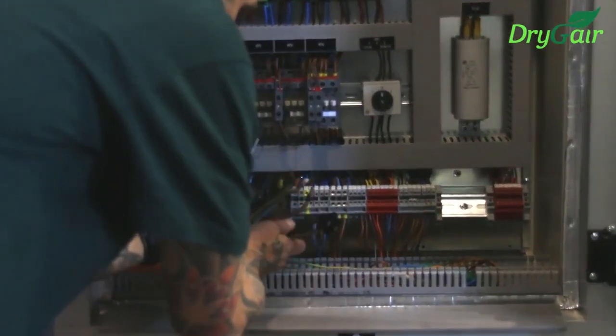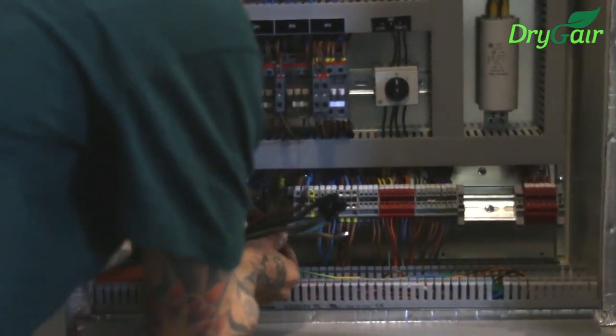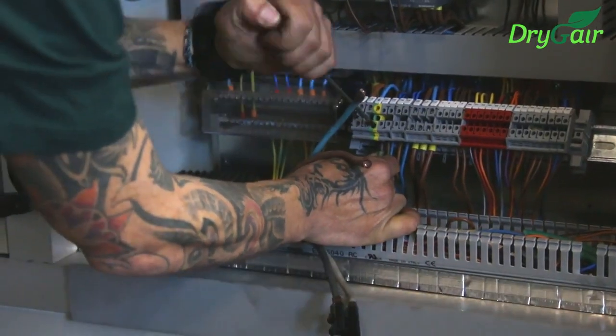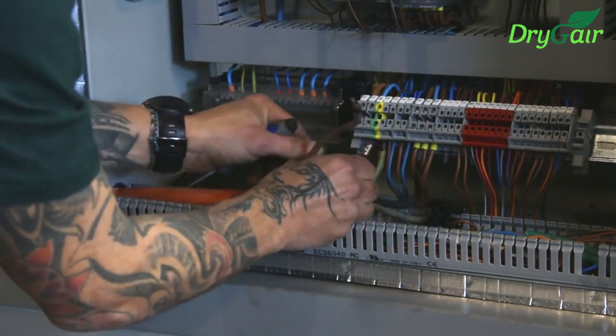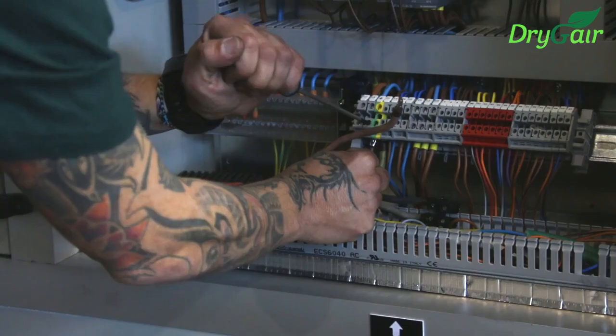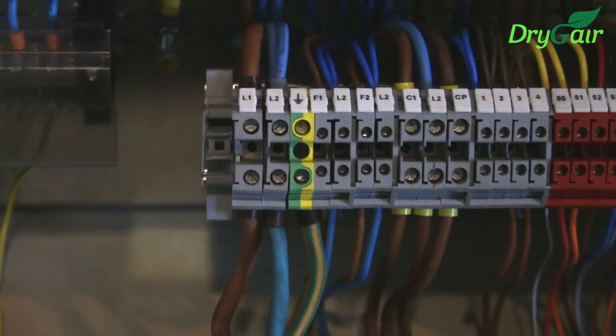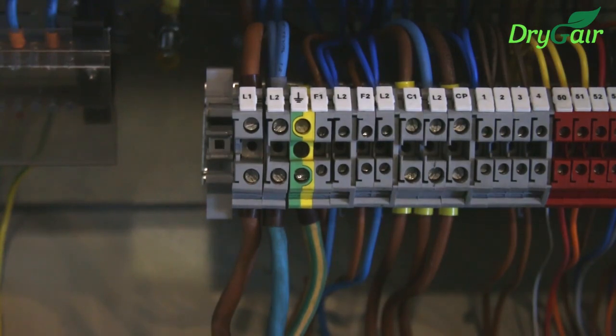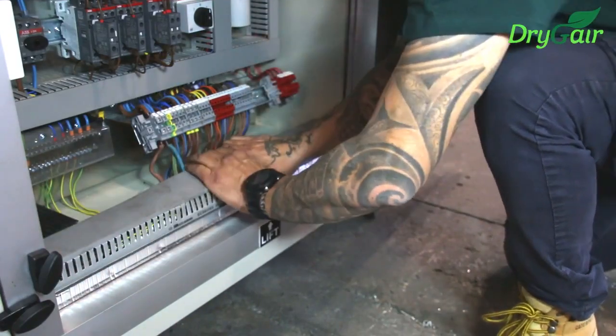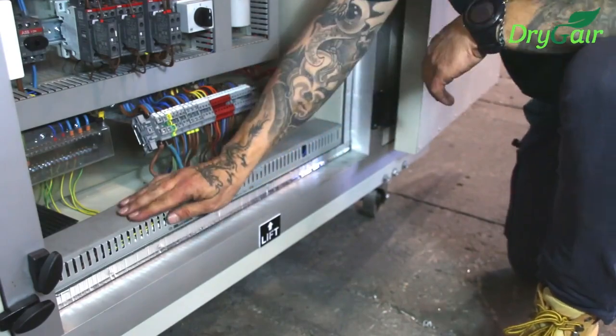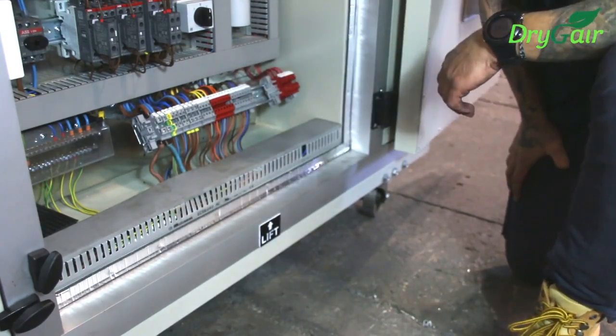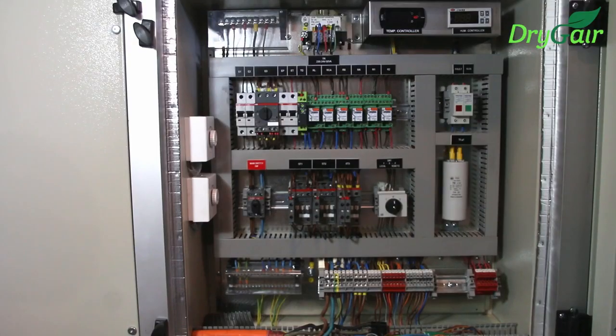Identify the grid connection terminal on the bottom row of the electric compartment. Connect the wires from the main power cable to L1, L2, and ground. When you're finished, it should look like this. You can return the cover back to the electric wire compartment. We are ready to power on.